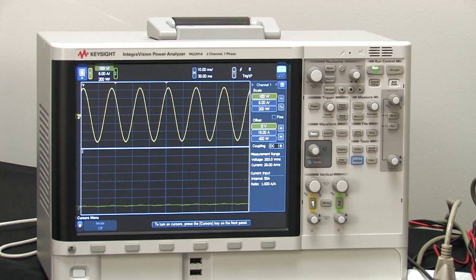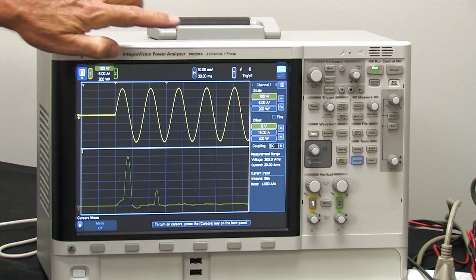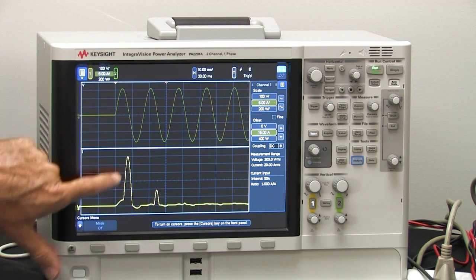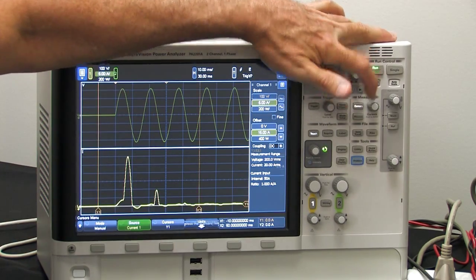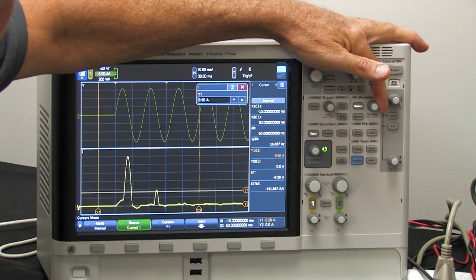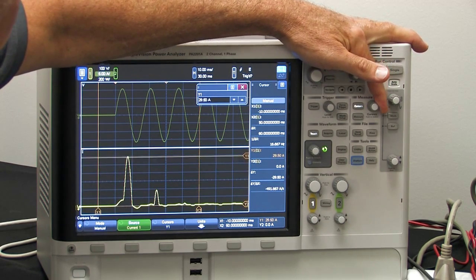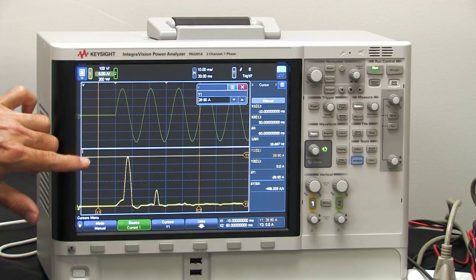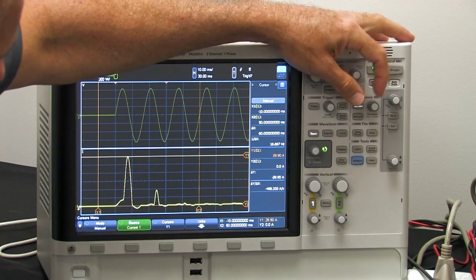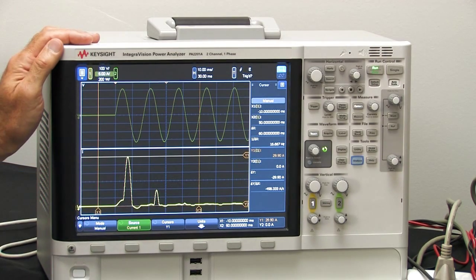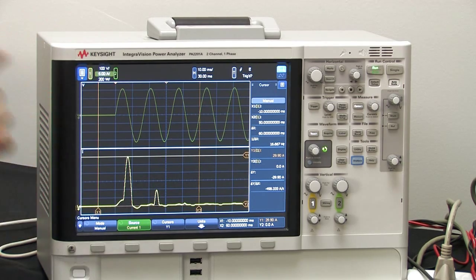Here's another really interesting AC power disturbance we can capture on a single shot basis. We can look at the AC inrush current of that DC power supply. I have my program set up to just go from zero volts up to an AC input. The AC should come on. It was sitting at zero and it went up and you can see this peak of inrush current that flows in. We can turn the cursors on to measure that and move that up and down with this knob. That peak of inrush current, this is at about 5 amps per division. 5, 10, 15, 20, 25, 30, and sure enough 29.9 amps. You can very easily capture a single shot with the IntegraVision power analyzer to see what the inrush current is.